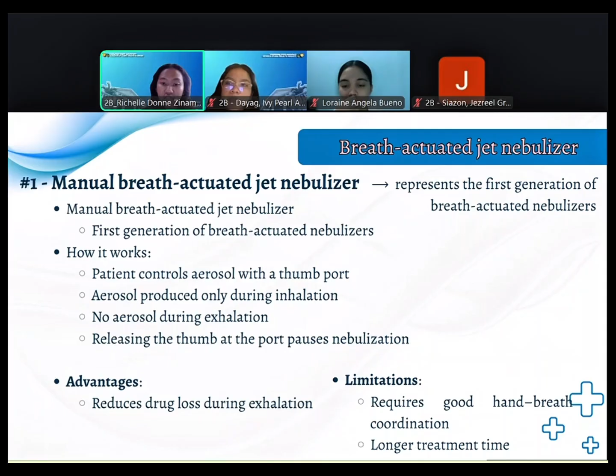Under the manual breath-actuated jet nebulizer, this represents the first generation of breath-actuated nebulizers. So it's very revolutionizing because it represents the first generation. It works where the patient controls aerosol with a thumb port, and the aerosol is produced only during inhalation. There is no aerosol produced during exhalation. And releasing the thumb from the port pauses the nebulization. Advantages include that it reduces drug loss during exhalation. Limitations: it requires good hand-breath coordination from the patient, and there is a longer treatment time.